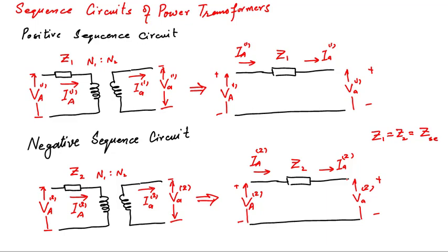So in order to mention the sequence equivalent circuit in that condition, we will have to add the phase in this turn ratio as well. We can add the phase shift here in turn ratio depending upon what type of phase shift we had in our circuit. For example, in positive sequence, according to IEEE standard, high side quantities will lead, so low side quantity will have this phase angle minus 30 degree. We will have to retard the low side quantities. Similarly, in case of negative sequence, the effect will be opposite to the positive sequence, so that will become advanced.